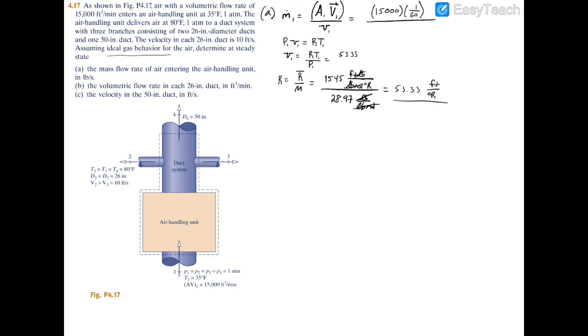The temperature is 35°F, so adding 460 gives 495°R. The pressure is 1 atmosphere = 14.7 psi, which converts to 2116.8 psf (pounds per square foot). Plugging into v1 = R·T1/p1 gives v1 = 12.47 ft³/lb. Dividing 15,000/60 by 12.47 yields the mass flow rate at duct 1 equal to 20.047 lb/s.